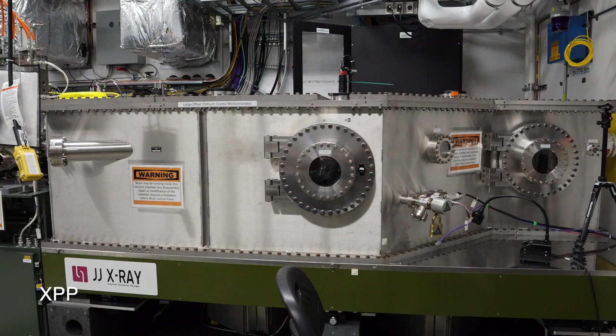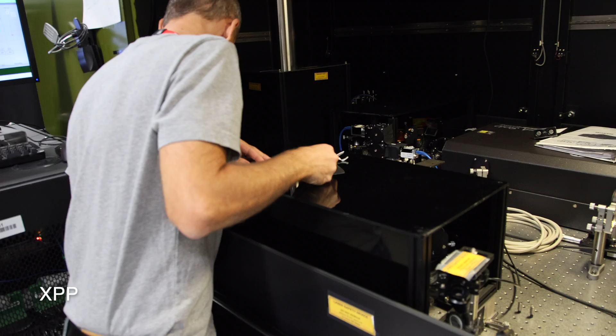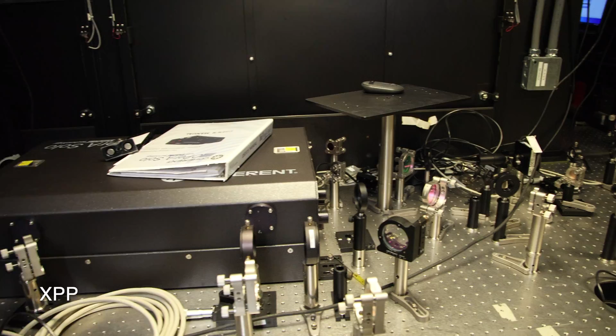Our fundamental laser system is an 800 nanometer titanium sapphire laser that can deliver up to 15 millijoule compressed pulse energy into the hutch. We can run either in a narrow band 100 femtosecond or a short pulse 50 femtosecond mode. We have high energy OPAs for near infrared and mid infrared conversion. We can also cover the visible and UV wavelength ranges.